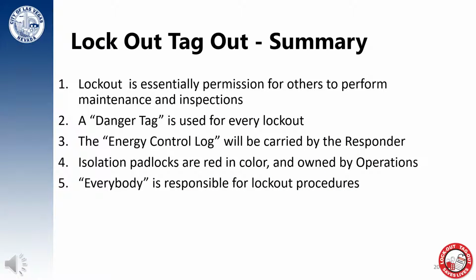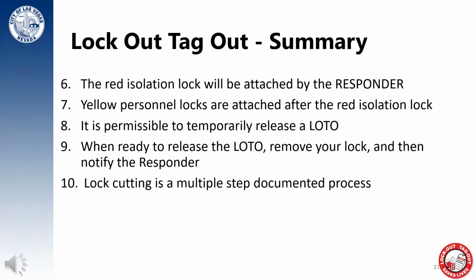In summary, lockout is essentially permission for others to perform maintenance and inspections. A danger tag is used now for every lockout. The energy control log will be carried by the responder. Isolation padlocks are red in color and owned by operations. Everybody is responsible for lockout procedures. The red isolation lock will be attached by the responder. Yellow personnel locks are attached after the red isolation lock. It is permissible to temporarily release a lockout. When ready to release the lockout, remove your lock and then notify the responder. Lock cutting is a multiple-step documented process.